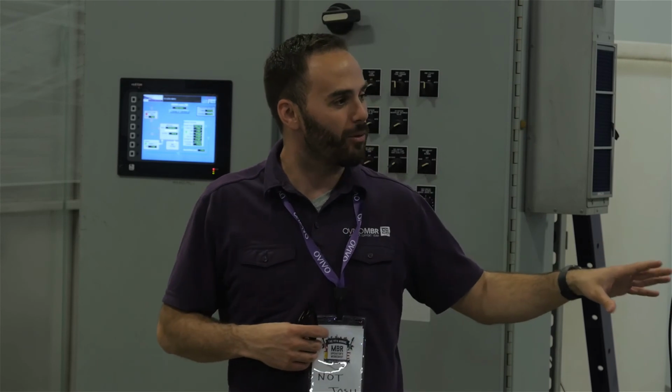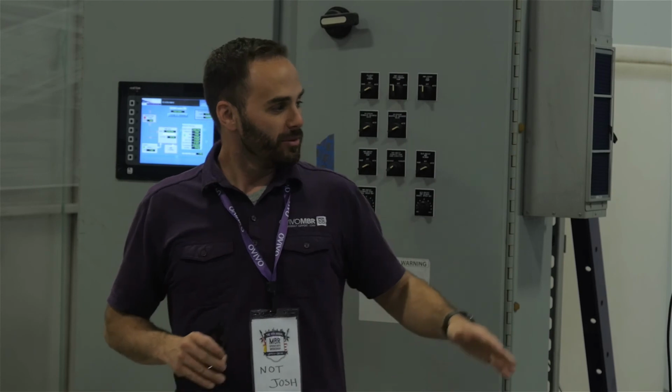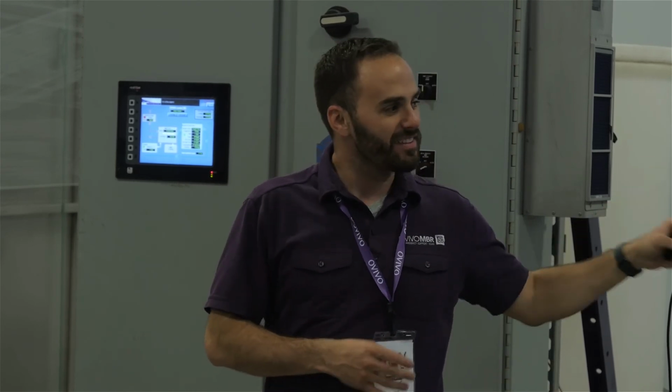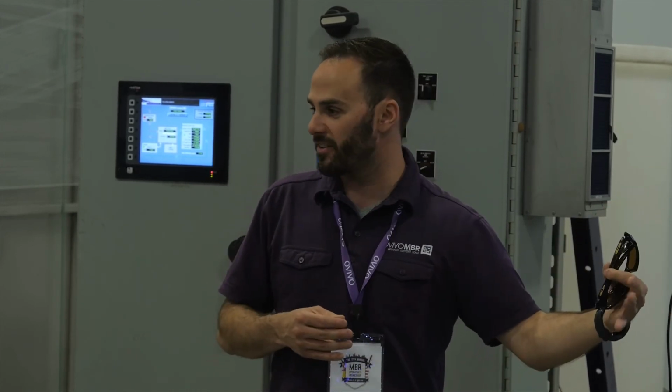Oh, and another note too, we didn't talk about where air can come in in this aspect, so I want to point this out as well. You've got to remember too, we're scouring the membrane all day long. Every drop of permeate that goes through there comes through while we scour. We are putting dissolved oxygen into the system in our pre-air system. That dissolved oxygen comes in with the permeate. So even if this thing is tight, it doesn't matter.